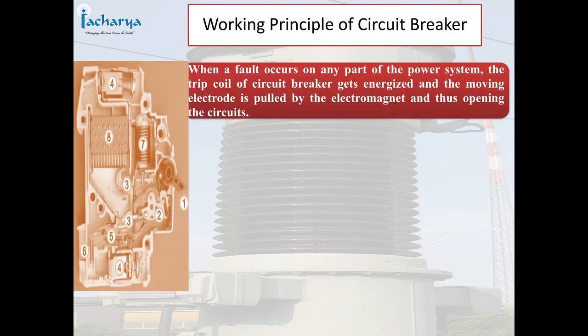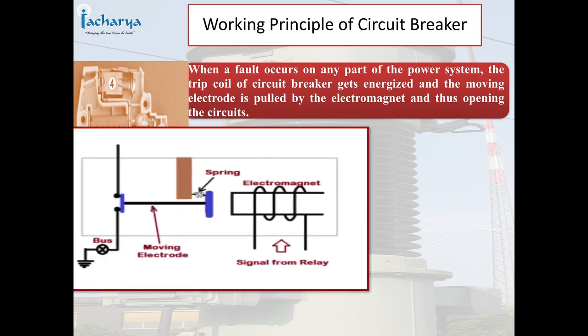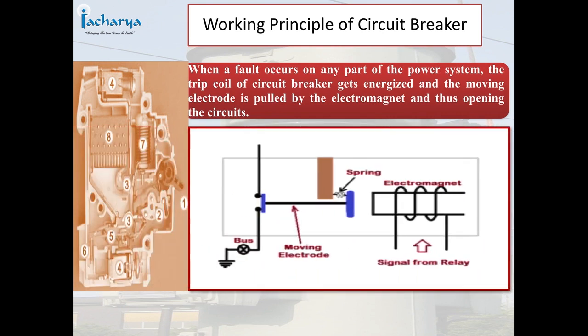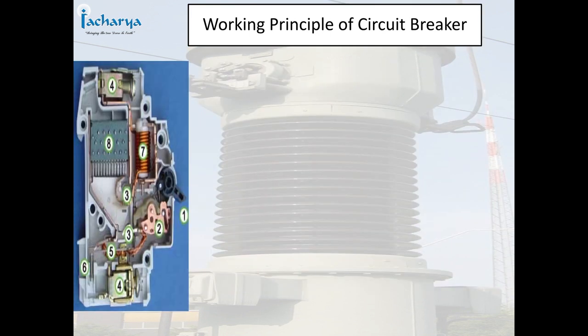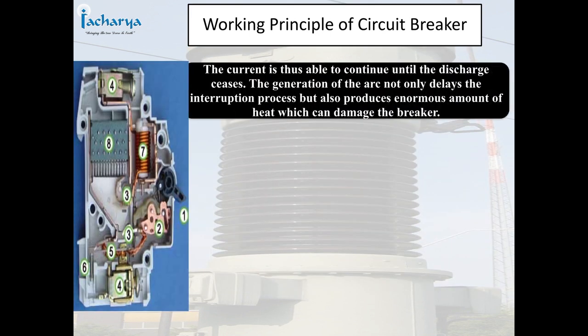When a fault occurs on any part of the power system, the trip coil of the circuit breaker gets energized and the moving electrode is pulled by the electromagnet, thus opening the circuit. The current is able to continue until the discharge ceases. The generation of the arc not only delays the interruption process but also produces an enormous amount of heat which can damage the breaker.